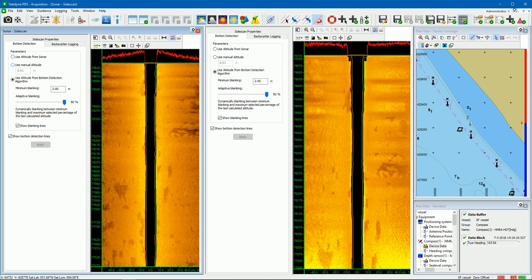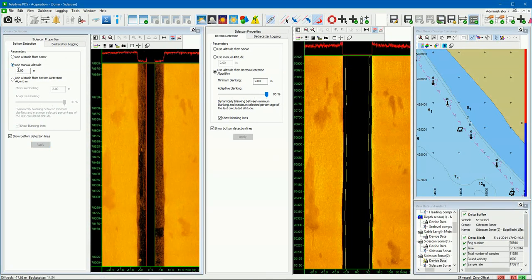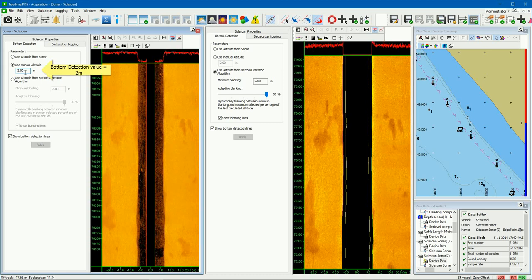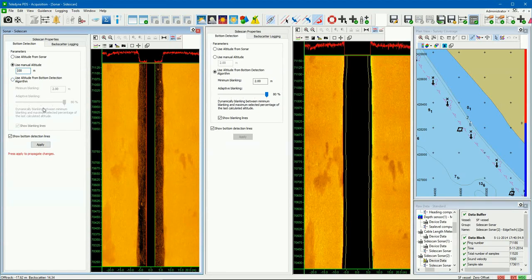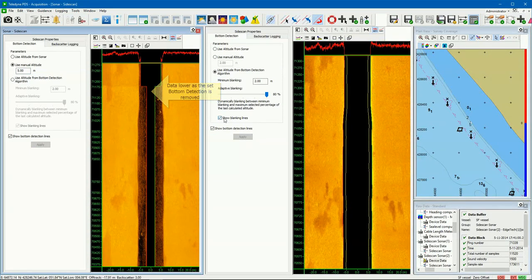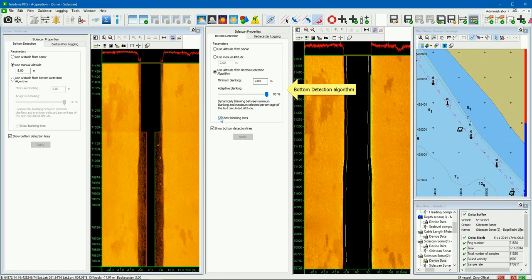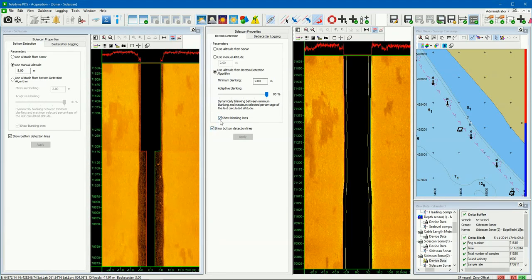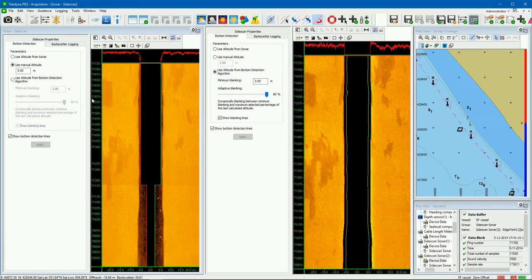In this mode the user can set a blanking distance — every value lower than the blanking distance is ignored as bottom detection. Furthermore, the user can set an adaptive blanking percentage. In the other view we can set the bottom detection for the other channel. If you use the manual altitude mode, the bottom detection is at the set value — now at 2 meters. If you change the manual value, the bottom detection changes accordingly. Data lower than the set bottom detection is removed and not shown.